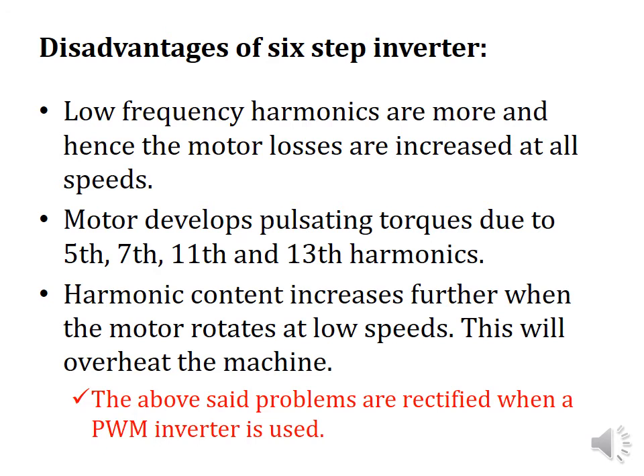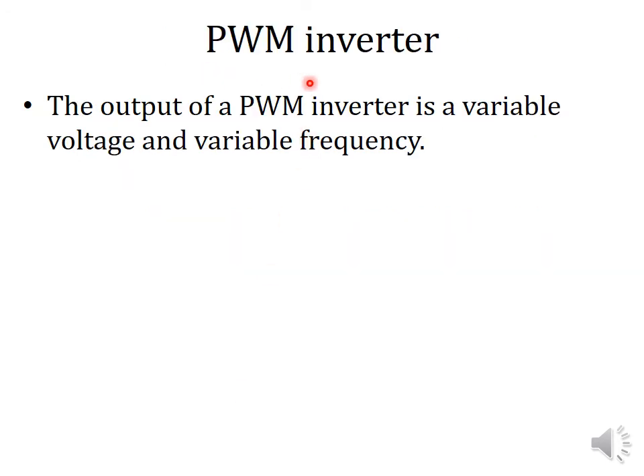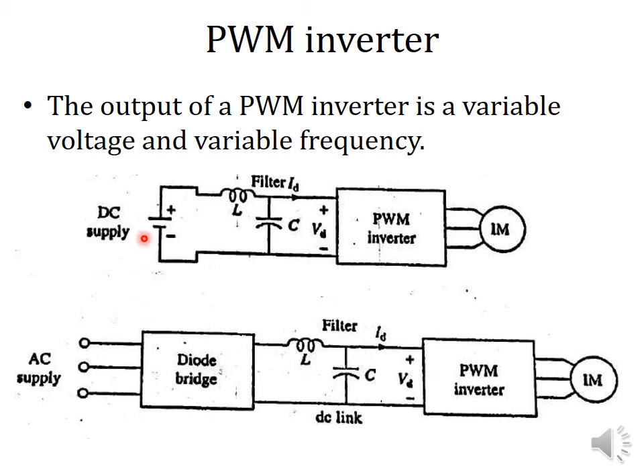To overcome these difficulties, we can use a PWM inverter. The output of a PWM inverter is variable voltage and variable frequency, meaning the PWM inverter is capable of controlling both voltage as well as frequency within the inverter itself. If the inverter has a fixed DC supply, it can be given directly to the PWM inverter, because the PWM inverter is capable of converting a fixed DC into variable AC voltage and variable frequency to provide the induction motor with V/F control.